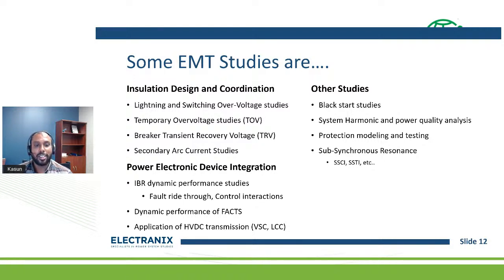So to see these issues, we need modeling in EMT, especially inverter based resources' dynamic performance, interactions with nearby plants, interaction with synchronous machines, and fault ride through, whether the inverters or devices will ride through temporary faults, and the dynamic performance of FACTS devices, especially HVDC transmission applications, and a few other studies like black start studies, system harmonics and power quality protection, and subsynchronous studies, and so on.